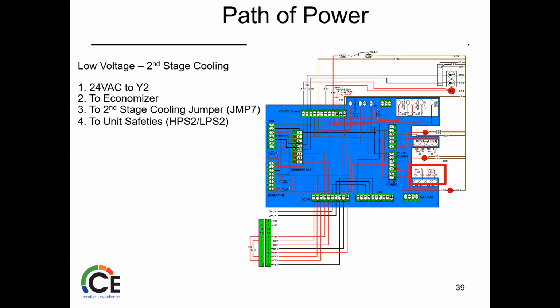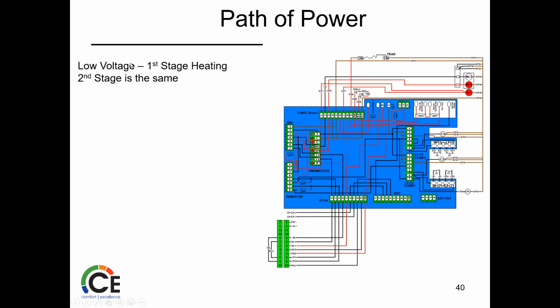Goes over, hits number 4 again on that CLO, 5 through the switches, back to 6. And it also energizes 7, saying, hey, I got a second stage call. I need more outdoor fan. Right there, need more outdoor fan. Off we go. So the path of power is exactly the same, right?